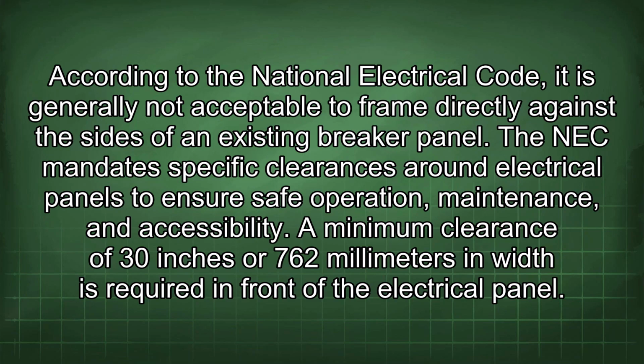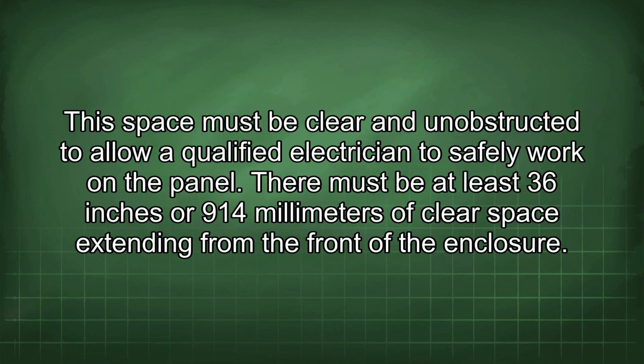According to the National Electrical Code, it is generally not acceptable to frame directly against the sides of an existing breaker panel. The NEC mandates specific clearances around electrical panels to ensure safe operation, maintenance, and accessibility. A minimum clearance of 30 inches or 762 millimeters in width is required in front of the electrical panel. This space must be clear and unobstructed to allow a qualified electrician to safely work on the panel.